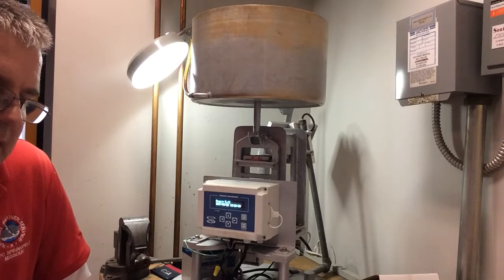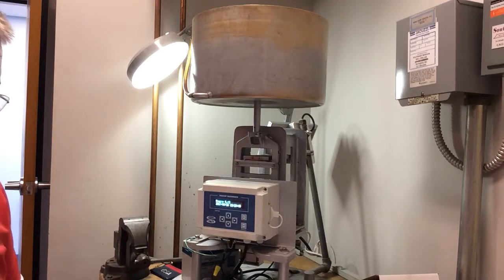For the Cal Test 0.5 inch equivalent range, which is one brass weight, the acceptable range is 4.75 through 5.24. So that looks good. We're showing 5 for that one. So for the next one, we'll put another weight in here.